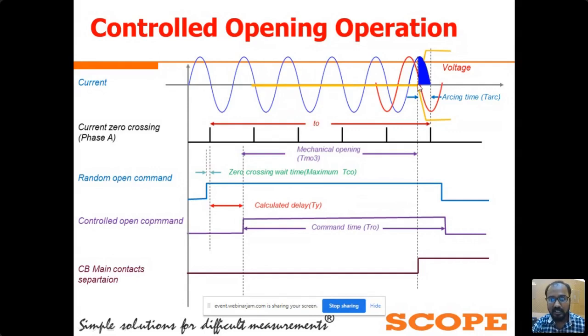At this moment we can see the dielectric strength between the CB contacts is less than the system voltage. Here the waveform in red is the system voltage waveform. So at this moment the dielectric strength between the CB contacts is less than the system voltage, and due to that, the current continues to flow at this point.